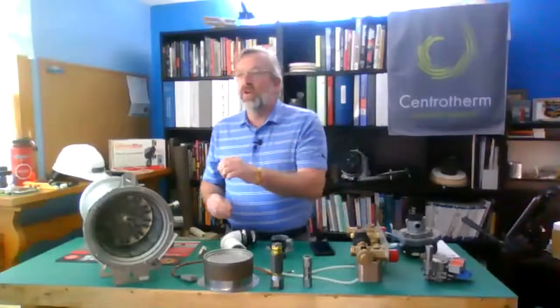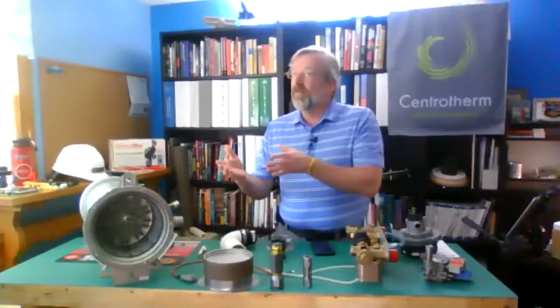Once we make a determination that we want to fire, what we do from that point in time is we really determine what the firing rate is going to be. So in a Noble, just about any of our boilers, there are two different sides to the brain. We have the I'm going to fire for heat, and we have the I'm going to fire for domestic hot water. Each one of those looks differently at what it's doing. Generally with domestic hot water, we're going to fire at higher temperatures and at higher firing rates, because we're kind of in a hurry to get there, to make sure that we're satisfying the domestic hot water load. So each side of the control is different, and it interprets it differently.